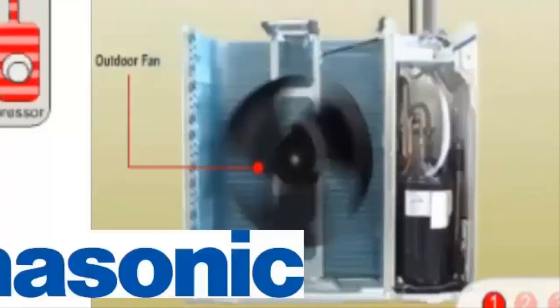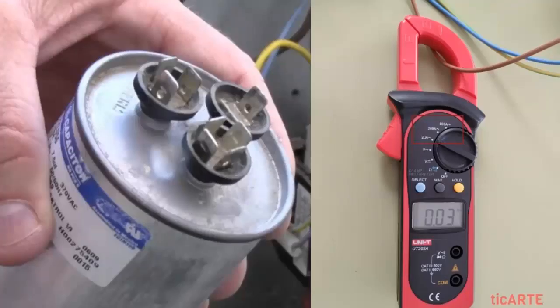3. If the ampere value remains high, it is good to check the compressor capacitor, replace it with another one, with the same technical specifications, and see if the issue disappears. Additionally, it is advisable to inspect the electrical connections, such as the contacts, voltage connections of the compressor, and compressor terminals. Look for hot spots that may indicate problems.